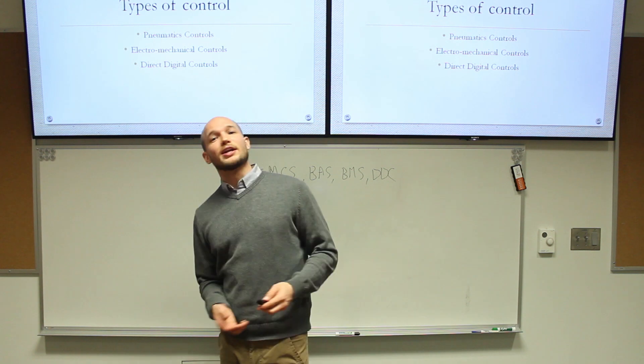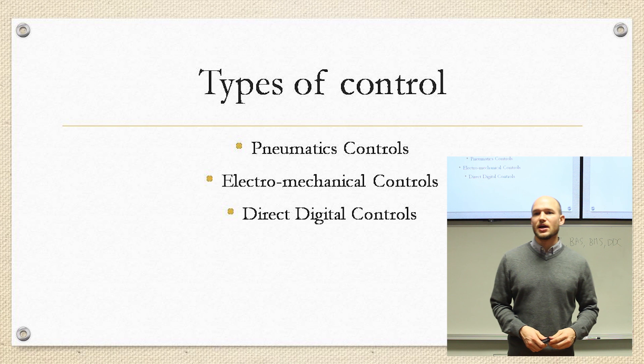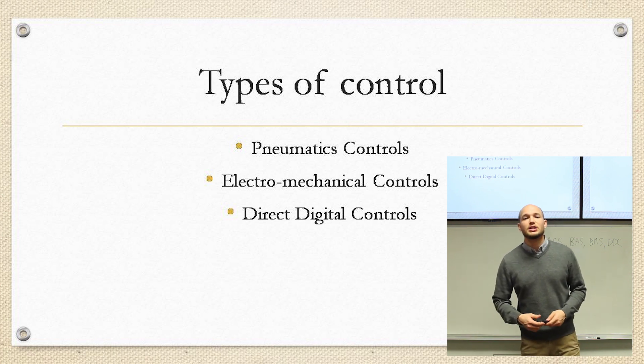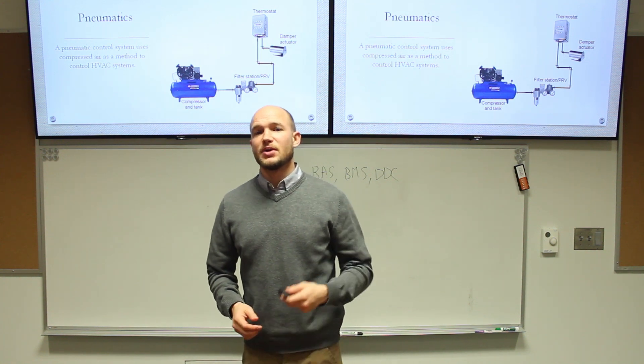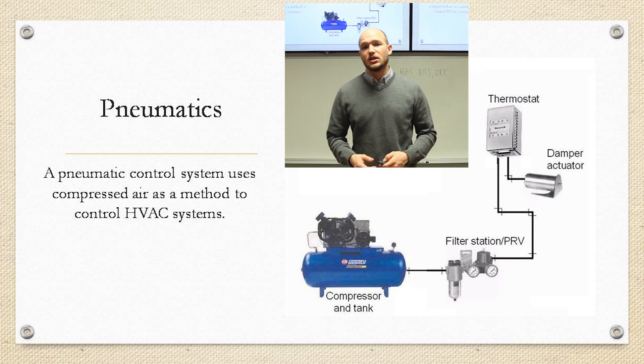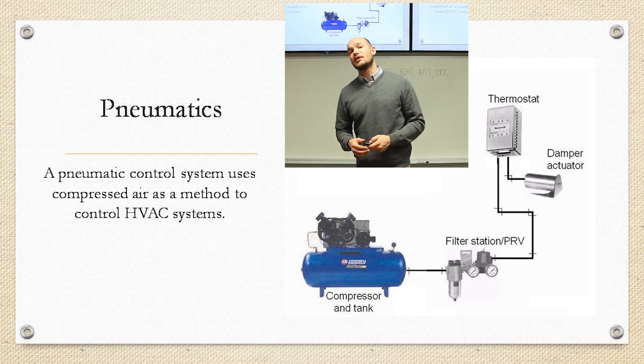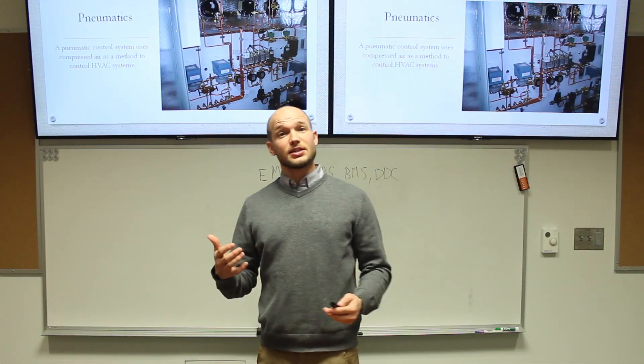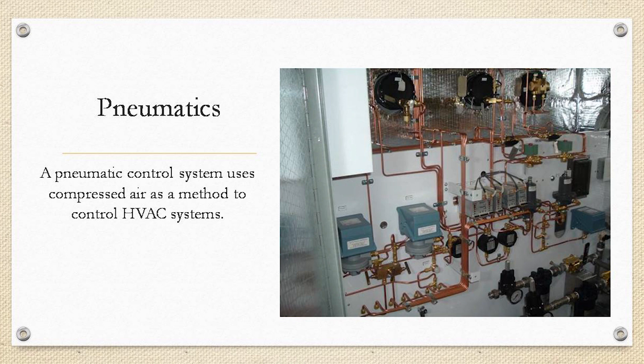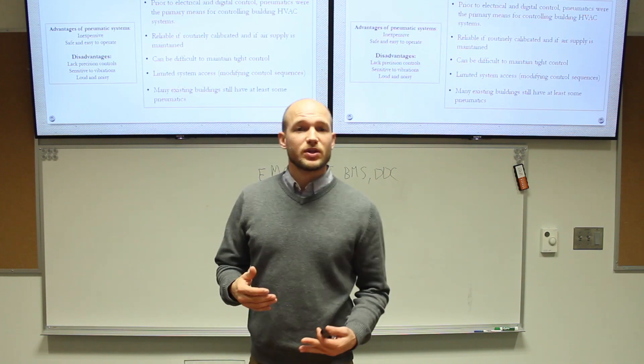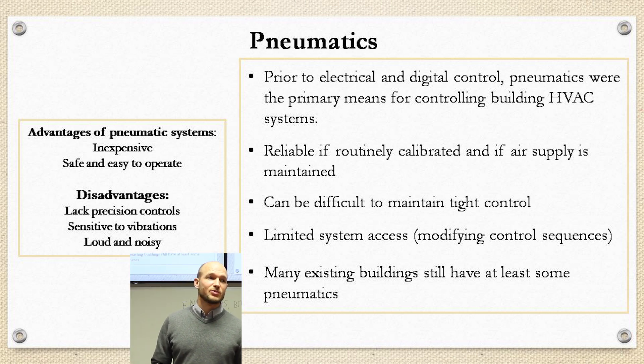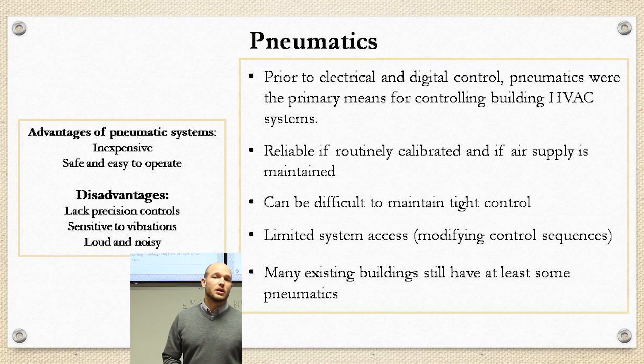There are three main types of controls to touch on: pneumatic, electromechanical, and DDC. Pneumatic was one of the first systems used to control HVAC. It uses compressed air — the drawing shown is a simplified version, but pneumatics can get very intense with a lot of tubing, piping, and places for air leaks. You're not going to see this system installed nowadays, but you will see it in the field when retrofitting or working on an existing building, as quite a few systems still use pneumatics.